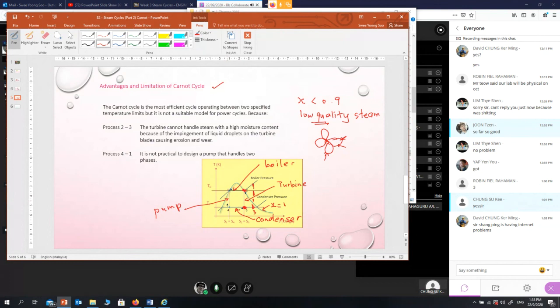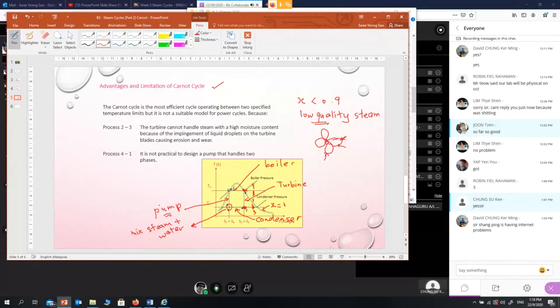The second limitation is at state point four — the inlet of the pump. At this point, the fluid is a mixture of steam and water (two phases). A pump can only handle a single phase — either completely water or completely steam. Pumping a two-phase mixture will damage the pump very quickly, so it is not practical to have state point four sitting inside the dome.